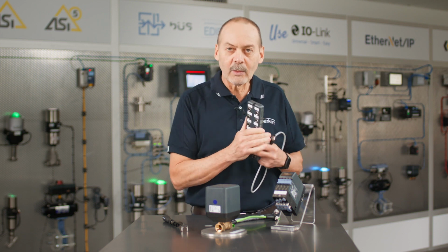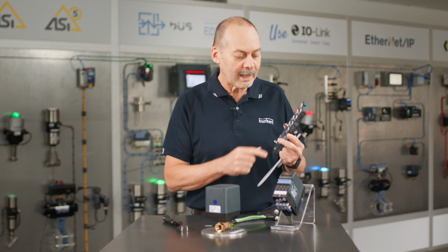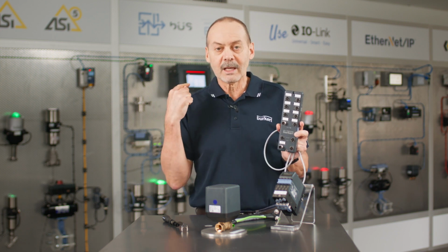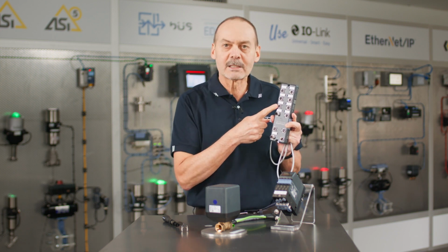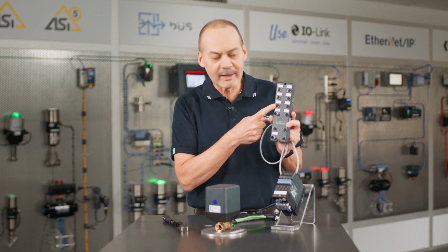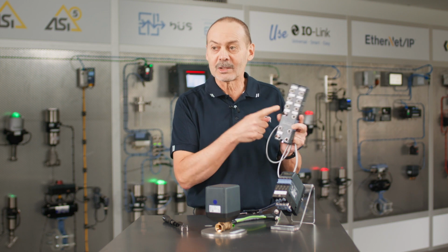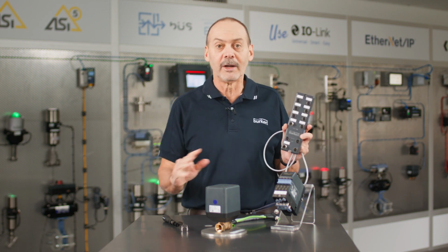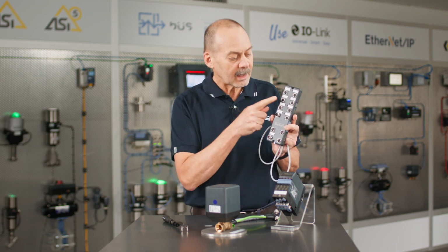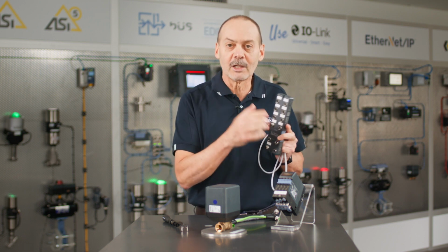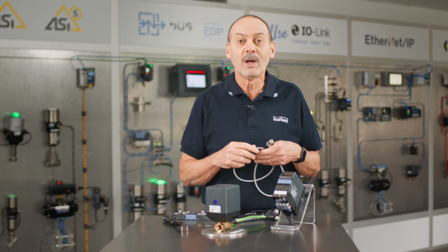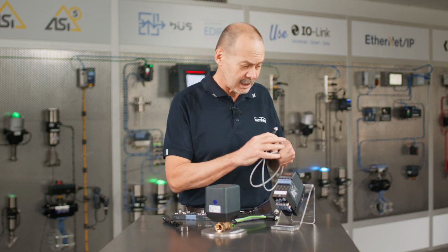Now, not on every network, but some networks, as an example, IO-Link, that port is assigned to the sensor in the field. If you put it back into the next port and you do the wrong one, then it's not going to work. And in the middle of the night, that could cause you a lot of downtime because you say it's plugged in, it's powered, the lights are on, but the PLC doesn't see it. So always label your cable, label its destination, so you know exactly how to do it. Just as you would with any good electrical installation, we need to do it with digital installations as well.